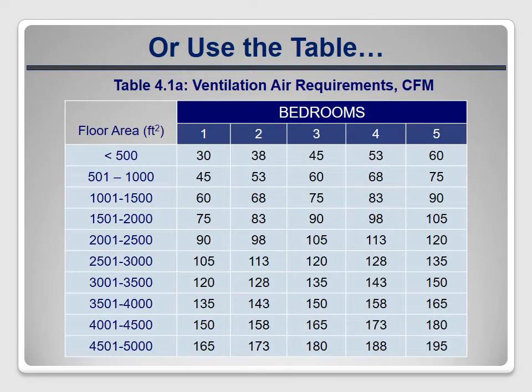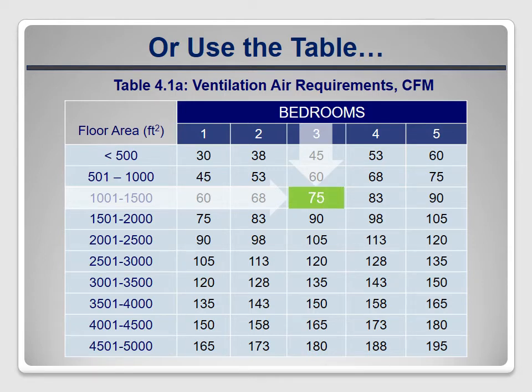ASHRAE 62.2 2013 also includes a table you can use instead of doing the calculations. You just find the row that includes the size of the house and the column with the number of bedrooms. Where the two intersect, it lists the required CFM, which is 75. Notice that in this case the number is higher than what we calculated — that's because it calculates based on the highest possible floor area in that row. In our case the house is 1200 square feet, but the table calculated for 1500 square feet. The standard has us over-ventilating again.